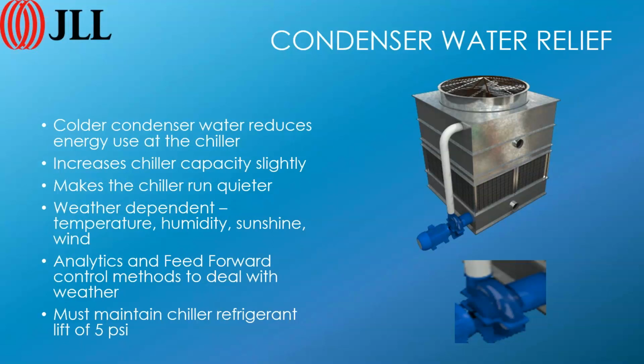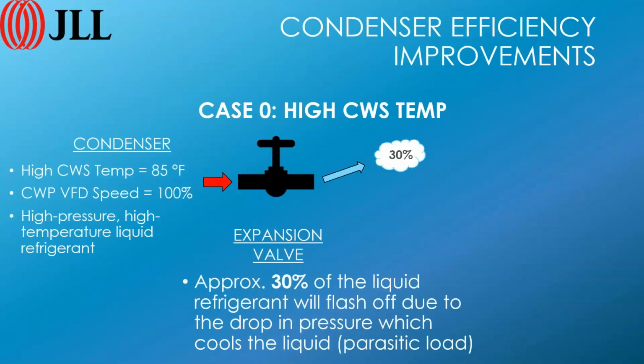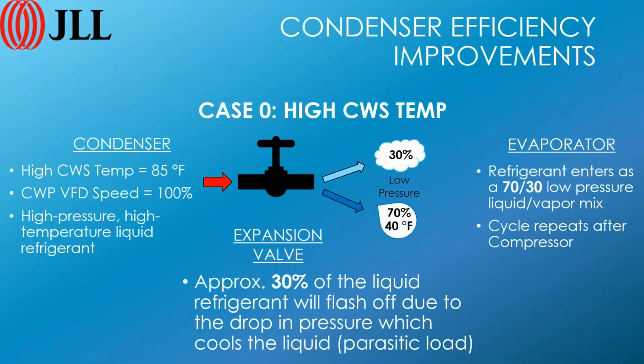We need enough pressure to push refrigerant out, and we want to cool it down enough so that we're flashing very, very little gas off. So this is the case that we're looking at. The normal case is around 30% of the gas getting flashed off in the condenser to make a 40-degree refrigerant, around a third, a 70-30 mix.